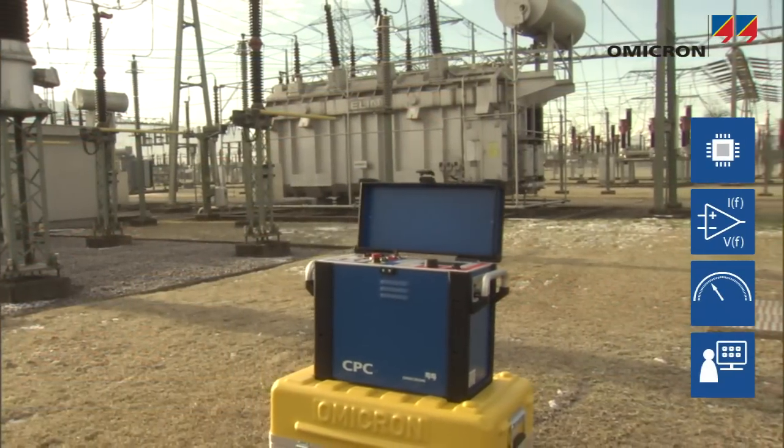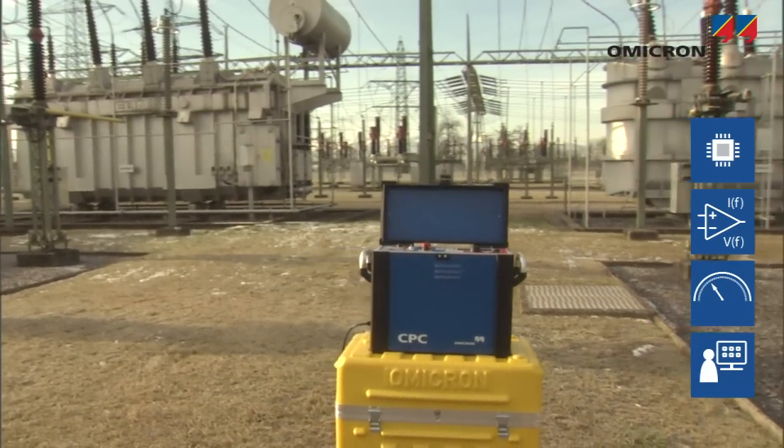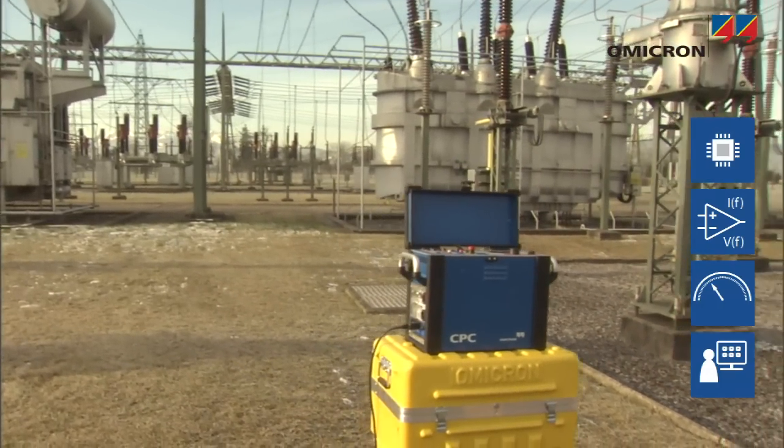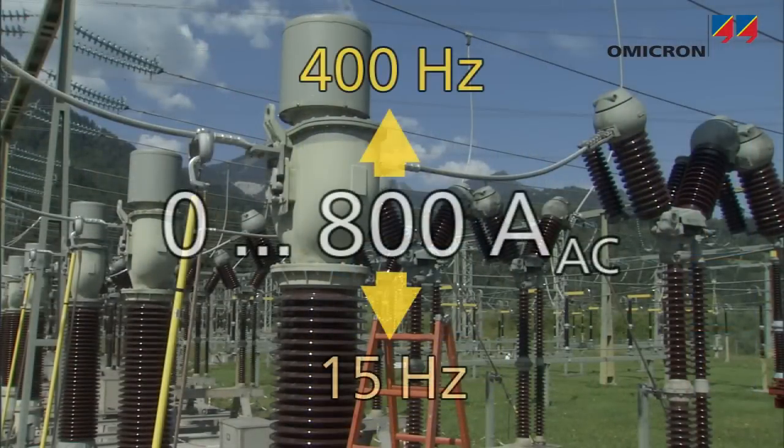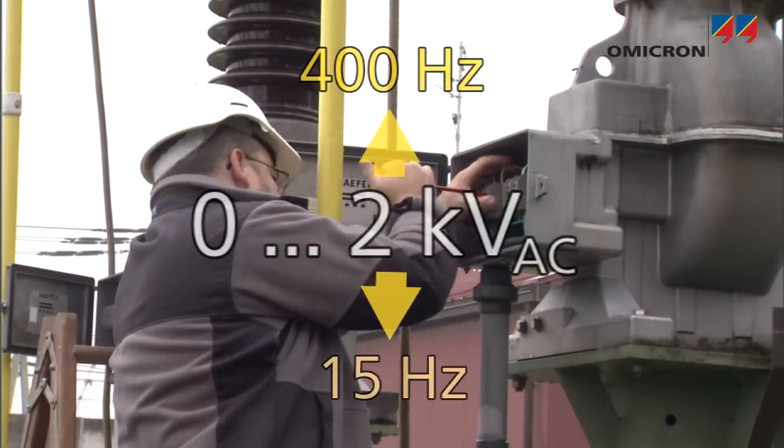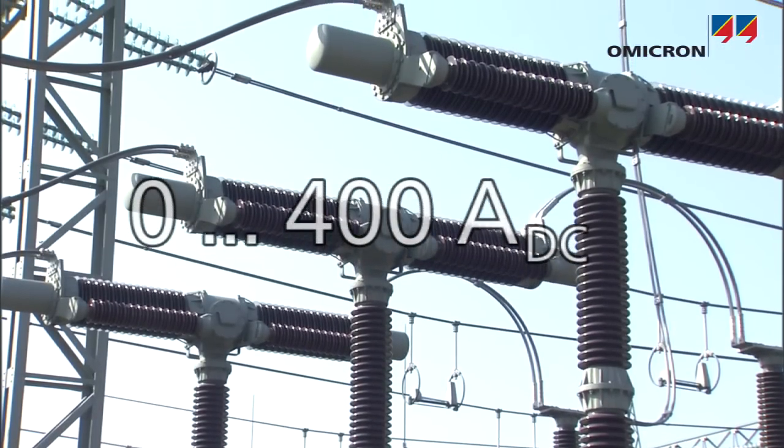The same technological basis is used in the CPC-100, a powerful multifunctional primary test set for substation commissioning and maintenance. It can generate up to 800 amps AC and up to 2000 volts AC at frequencies ranging from 15 to 400 hertz and up to 400 amps DC.